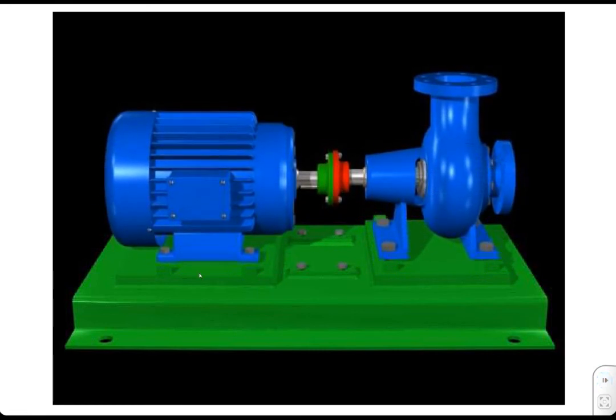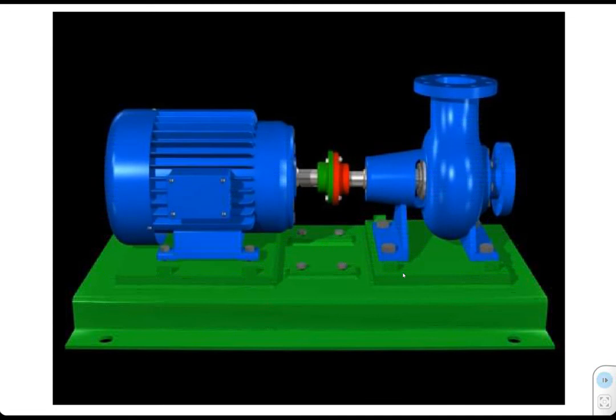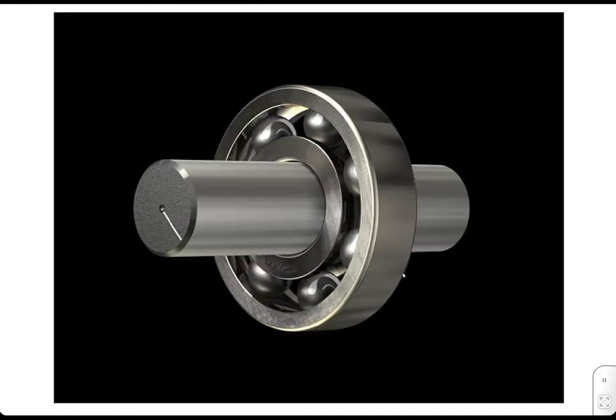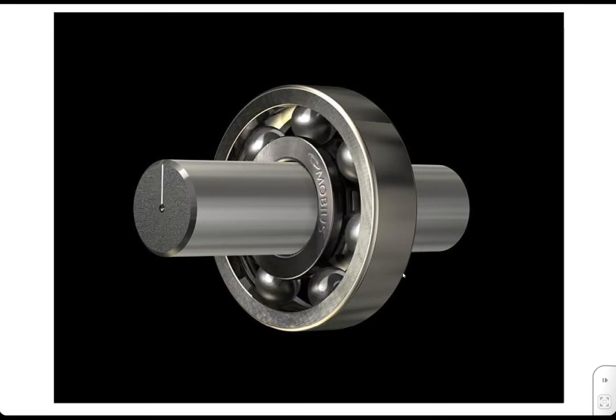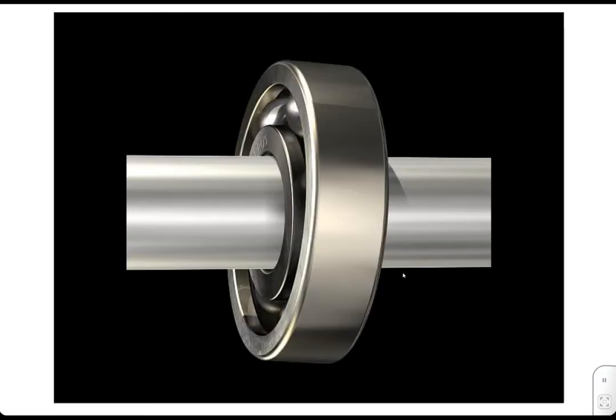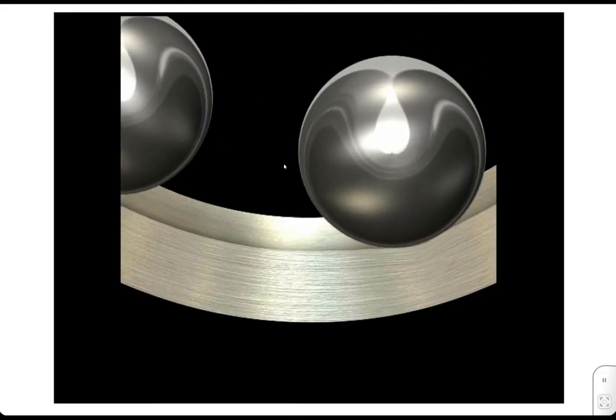And all that vibration also transmits down into the base and the foundations, and it can harm that as well. If the bearing isn't installed properly and it's just cocked on the shaft, then that will reduce life as well. If the bearing was cocked in the housing or there was angular misalignment, that puts all sorts of extra load on these rolling elements. Even if it's just cocked by a little bit, it reduces the life of the machine.